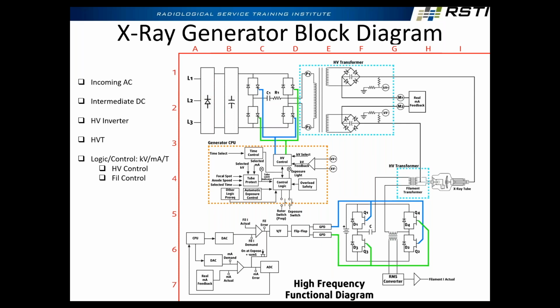So we're taking AC and converting it to intermediate DC. This guy right here is called the high voltage inverter. I'm going to pass this DC through this guy. This is the high voltage transformer. You can't pass DC through a transformer. Everybody agree? So what do you think this inverter now is doing with this DC?